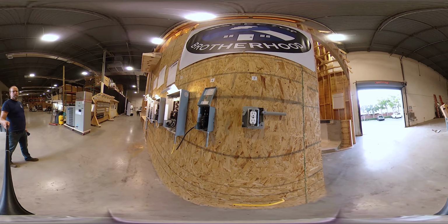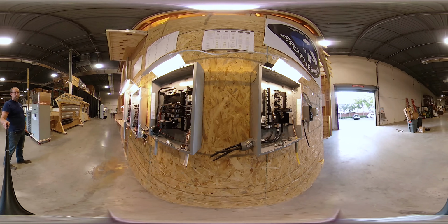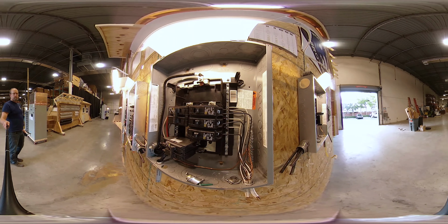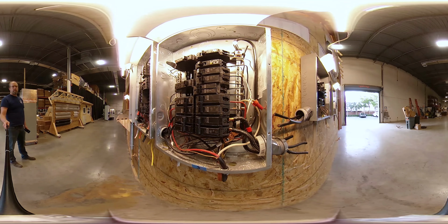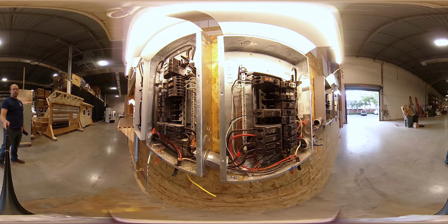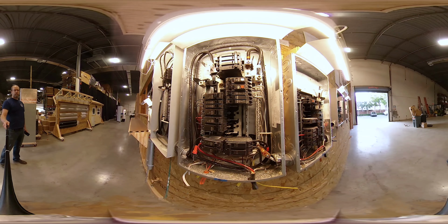Back to the electrical panels. There are 7 systems here, all the way down from the service through the electrical panels down to the device or receptacle. We take a look at the neutrals and the grounding and how the sub panel is supposed to look, and properly installed or improperly installed. What are things like red taping? Is that proper? There's an AFCI and a GFCI.